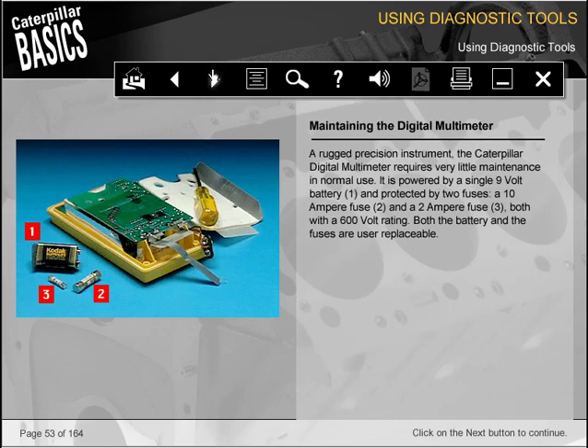A rugged precision instrument, the Caterpillar digital multimeter requires very little maintenance in normal use. It is powered by a single 9-volt battery, 1, and protected by 2 fuses, a 10 ampere fuse, 2, and a 2 ampere fuse, 3, both with a 600 volt rating. Both the battery and the fuses are user replaceable.